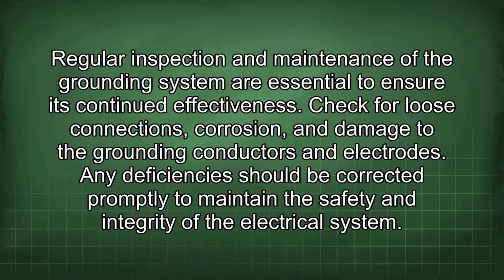Regular inspection and maintenance of the grounding system are essential to ensure its continued effectiveness. Check for loose connections, corrosion, and damage to the grounding conductors and electrodes. Any deficiencies should be corrected promptly to maintain the safety and integrity of the electrical system.